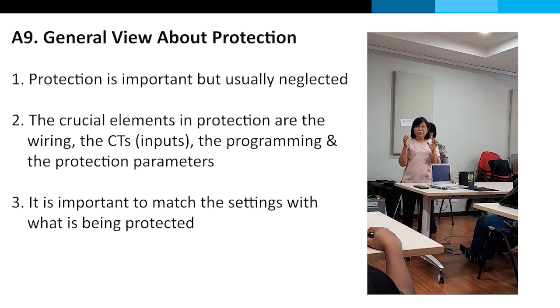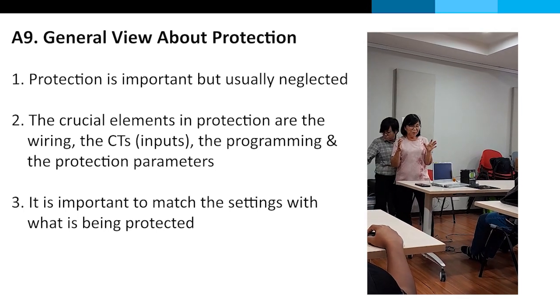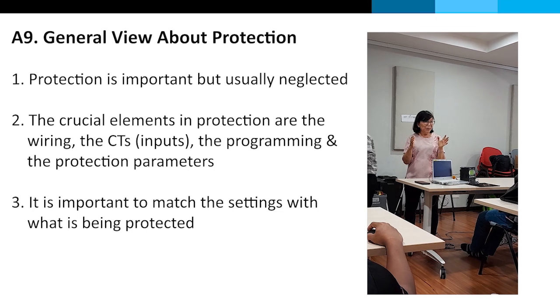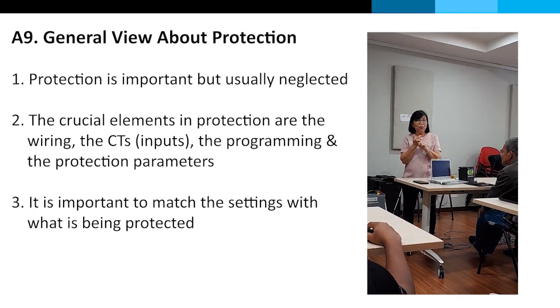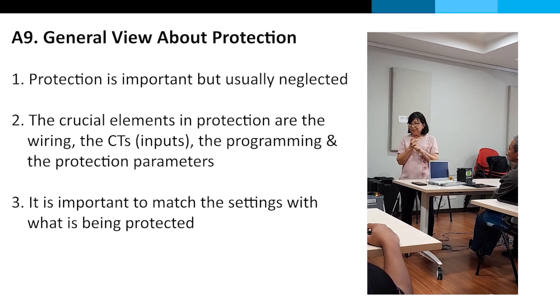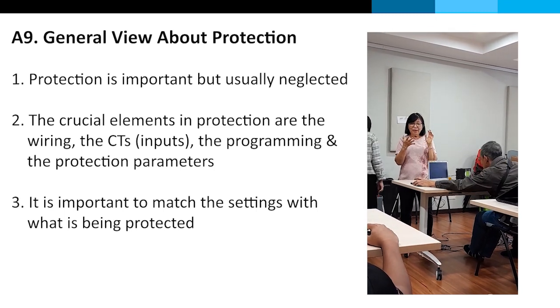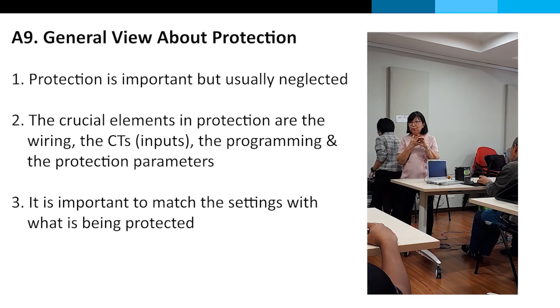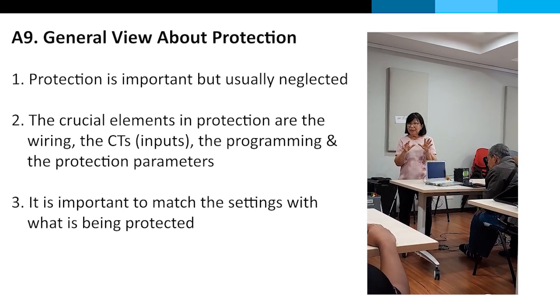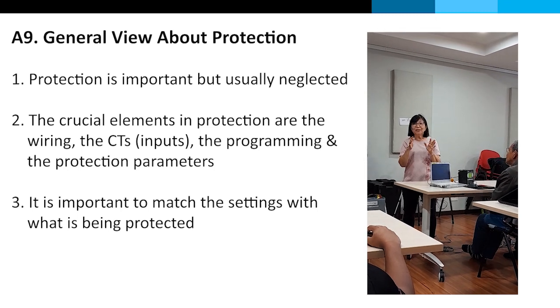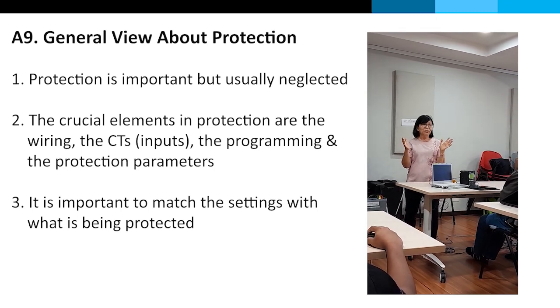So actually for protection, walaupun it's very simple, tak berguna, but when you need it, it's very important. Okay, so number one, wiring is important. The way you use it, your CTs are important, your inputs are important. So lepas itu you program it correctly. Then lepas itu what setting you give. Kalau you give wrong setting, sudahlah.